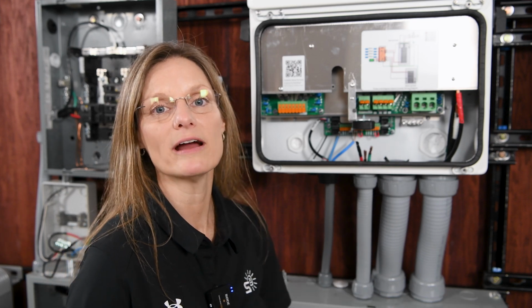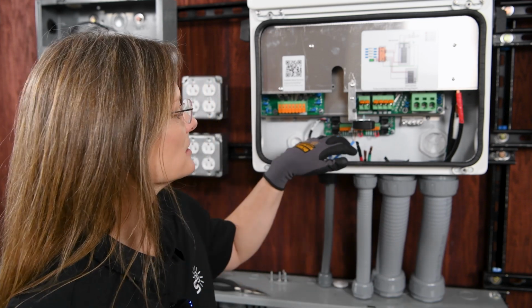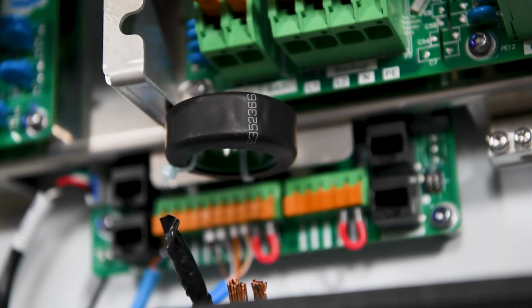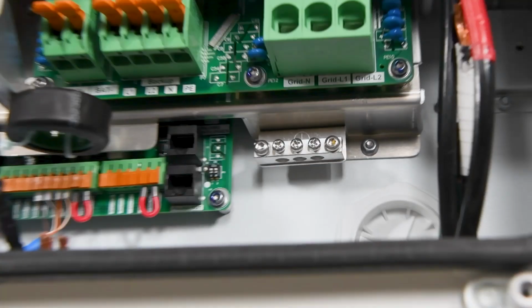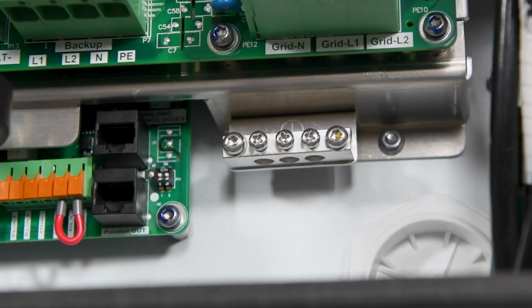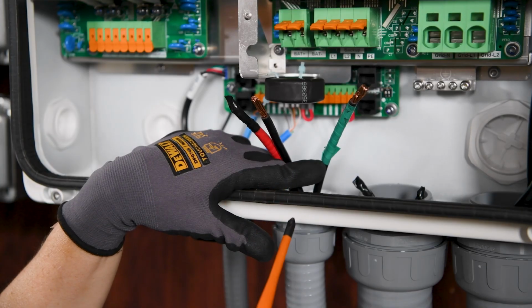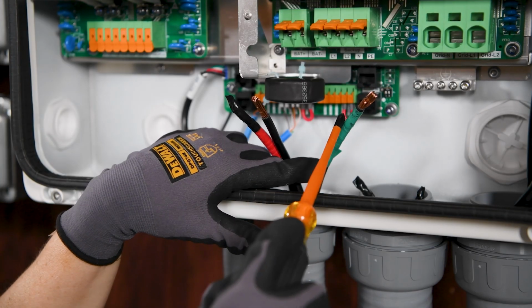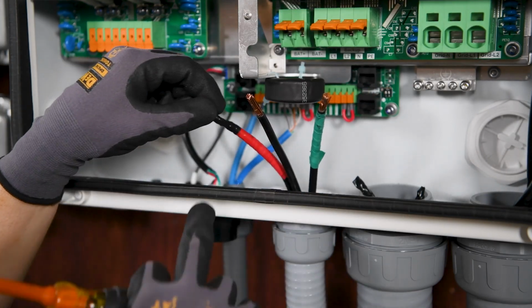Now we're ready to connect our battery cables. So we've got a positive and a negative and a ground that we will connect. Our positive and negative will go up through the filter into our battery terminals, and our ground will go over to our ground bus bar. Now our battery cables, our power cables are not connected to our batteries yet. We'll do that after we connect them in the inverter.